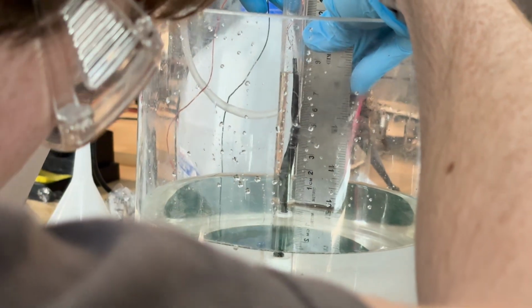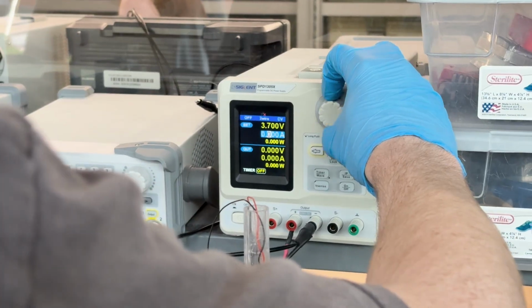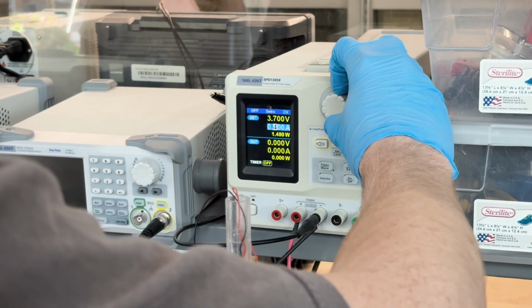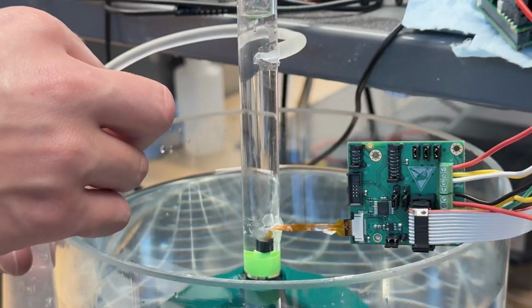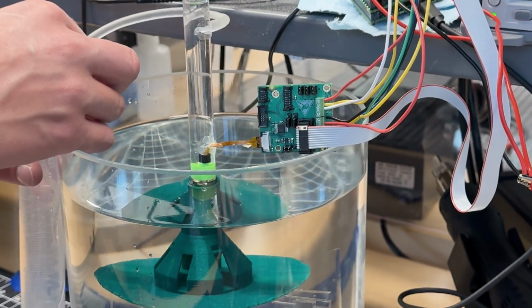To verify our impeller design, we removed the wireless power transfer variable and used a wired motor prototype to isolate the performance of the impeller. Using a high-efficiency Maxon motor, we were able to exceed our pressure head requirement of 6.59 millimeters of mercury, while the motor consumed 120 milliamps of current.